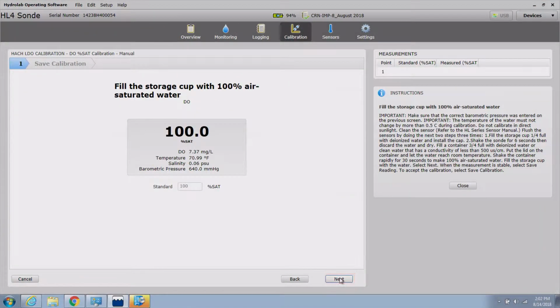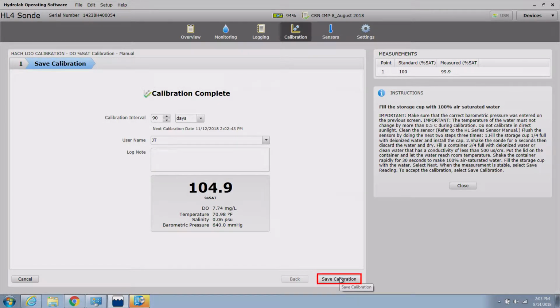Click Next to proceed. The stabilization process will begin and must complete successfully before the calibration can be saved. When the measurement is stable, select Save Reading. To accept the calibration, select Save Calibration.